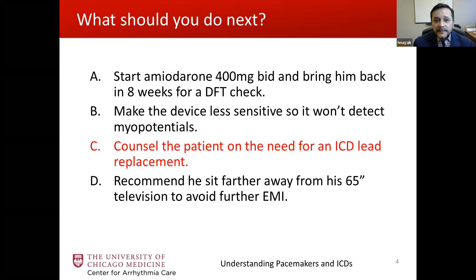Now, remember that lead fractures cause oversensing of noise, and may lead to inappropriate shocks. And Dr. Singh had a wonderful case where it can not only lead to an inappropriate shock, but also inhibit pacing. So in someone who is pacemaker dependent, the patient suffers a sort of double whammy. They can get a shock, and then they can also have asystole. Now, lead fracture typically causes elevated pacing threshold and pacing impedance values. And as we saw in the example, there's intermittent sensing of high frequency, non-physiologic signals, particularly when the patient assumes certain postures. And sometimes you can bring that fracture out by manipulating the patient's arm. Many times there's a make or break type of situation, or a microfracture that can really be brought on with changes in posture and position.